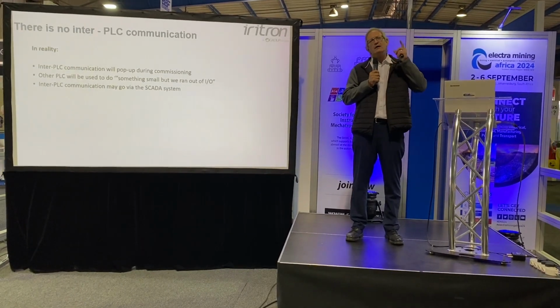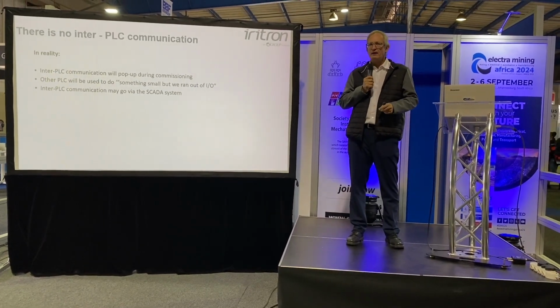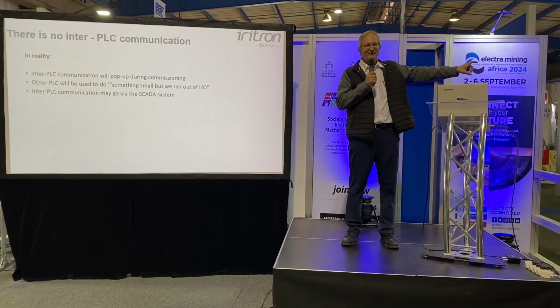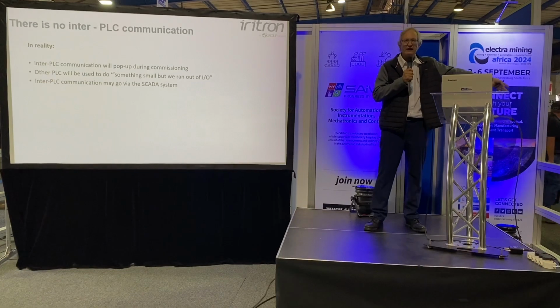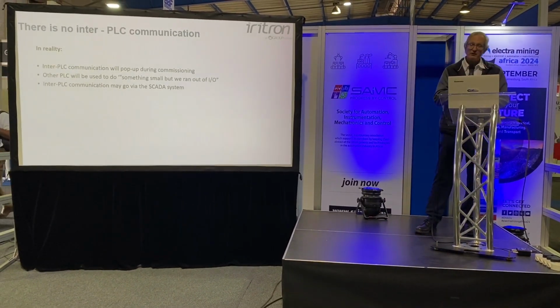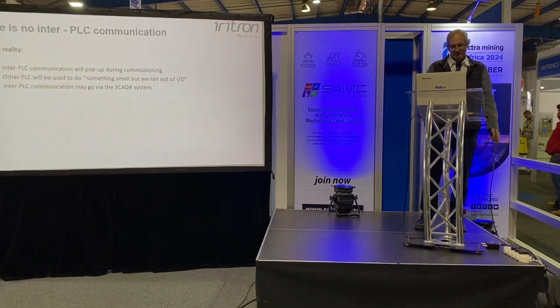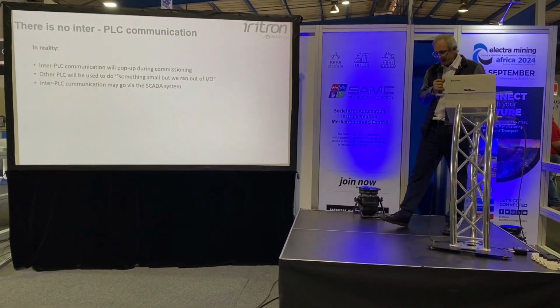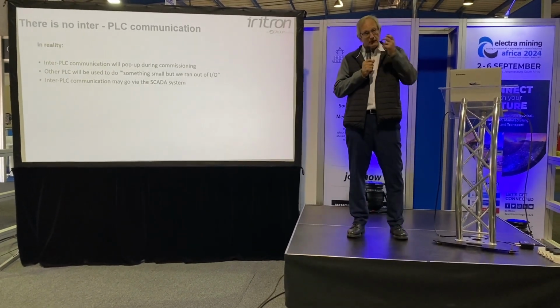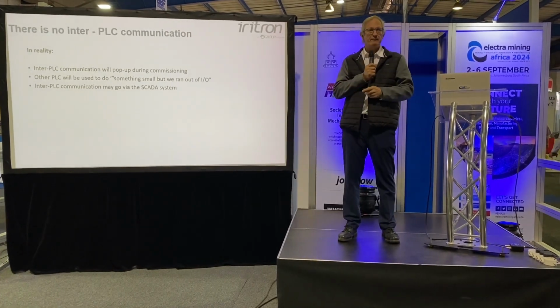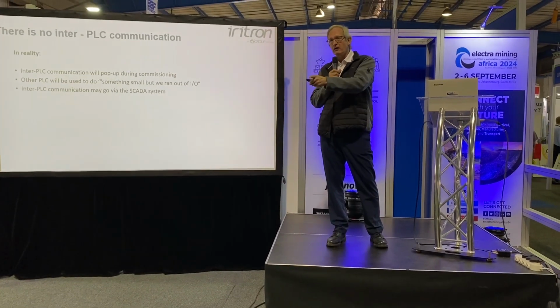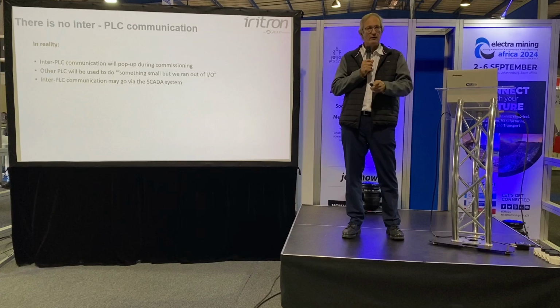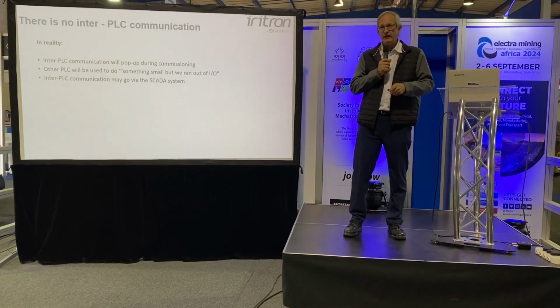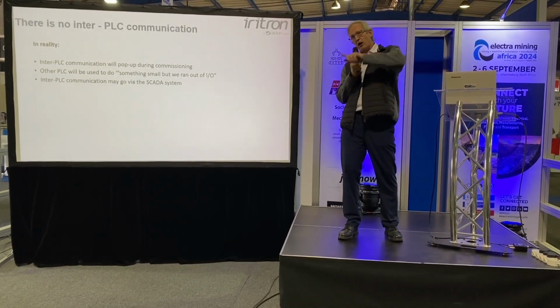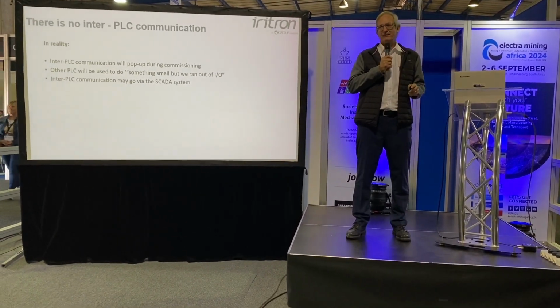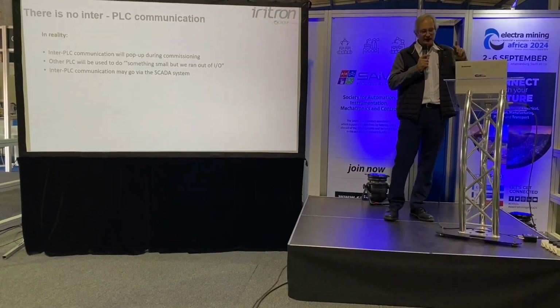And then they say, okay, yes, we had a problem with the number of I/O available on this PLC. So we did this little recipe management thing in that PLC. Sorry, we forgot to tell you when you actually did the original design that we actually do have inter-PLC communication, which is something you don't want to hear when you're sitting in the plant at 1 o'clock in the morning. And in addition, that PLC is on a different communication protocol than this PLC. So we're not talking Profibus to Profibus or Profinet to Profinet. We're getting the information from the PLC, putting it into our I/O server and transferring it through the I/O server into the other PLC. So instead of doing it the right way, we do it in a let's make it work way.